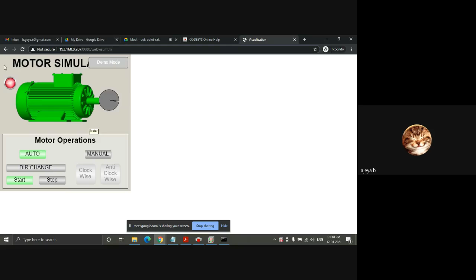So what this means is that your laptop, what is connected to the network, right? In that network, any device which has a web browser can put your laptop's IP and this link and open it in their browser and then visualize the HMI. So any devices in the same network will be able to visualize this HMI and not just visualize, control also. So it will be able to control, start, stop the motor. So whatever your laptop, that is the PLC right now, whatever that PLC is doing, the whole control is given through the web visualization, through the browser, to whoever has that link, and then he can connect to the PLC and visualize the HMI through his web browser and then control it.